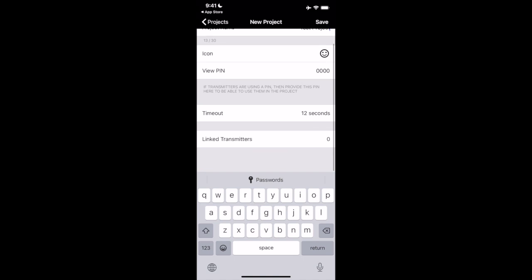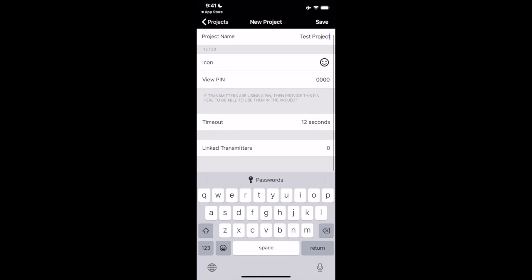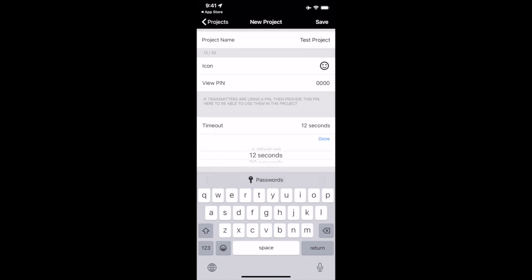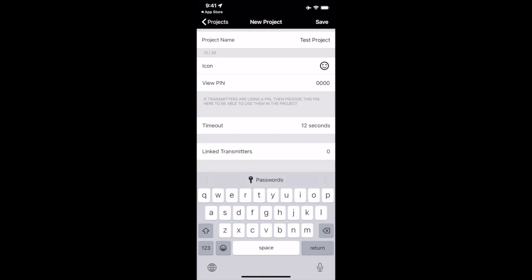The timeout section just below where it is currently at 12 seconds, I have options to go from all the way from one second up to 30 seconds. So I'll leave it the default 12. What timeout is, is when we're viewing the information, timeout is the amount of time without receiving data from the load cell, whether it's out of range, you removed a battery, any of the such, until our display tells us that we are out of range.